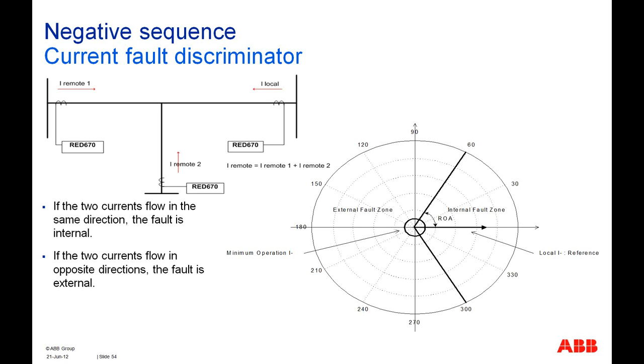So if these negative sequence currents are flowing in the same direction, then the fault is internal. And if the two currents are flowing in the opposite direction, then the fault is external. So the local current phasor is taken as a reference, and the remote current will be compared with the local current, and the angle between these two measured phasors for the negative sequence currents will be taken into account to find out the direction or the location of the fault.